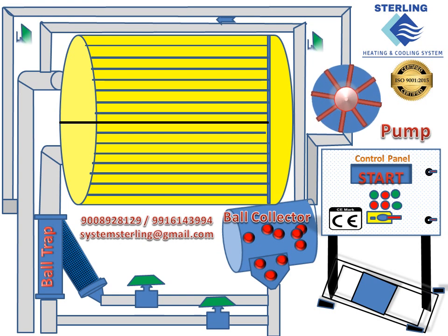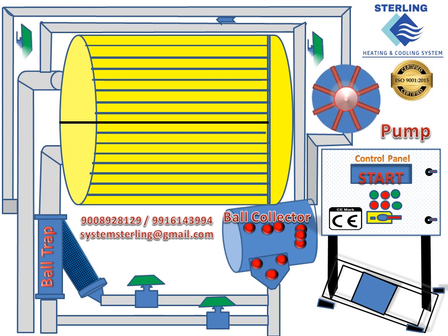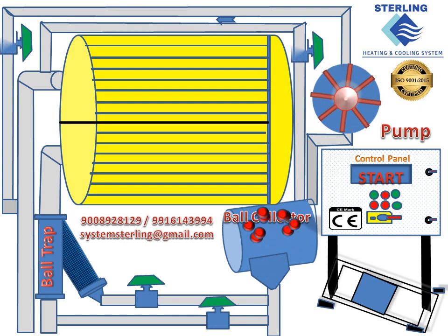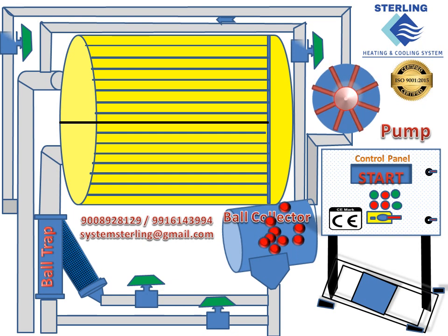The auto-tube cleaning system starts with the water pump of the condenser tube cleaning system, pumping the balls from the ball injector to the water inlet of the condenser. The balls enter the end cover of the condenser along with the circulating cooling water and get into the copper tubes of the condenser randomly, driven by the circulating cooling water.